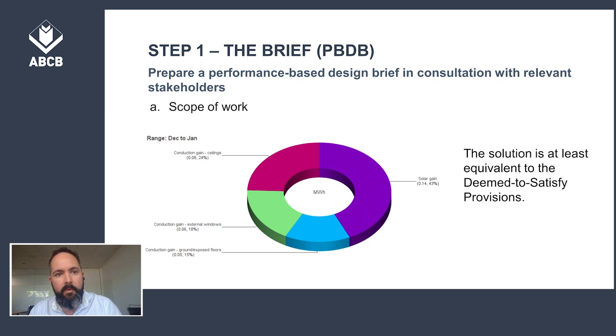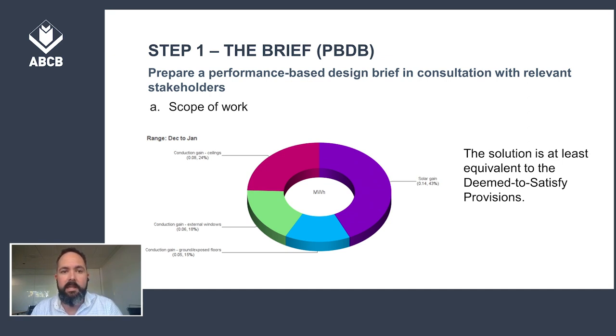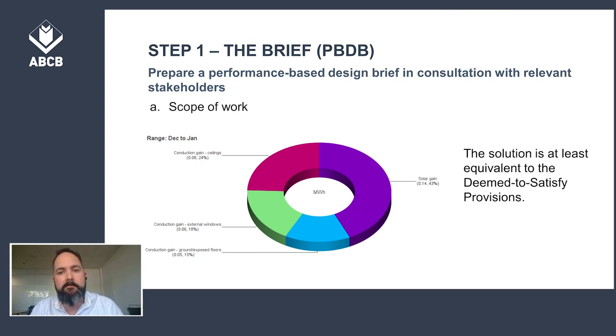Step one: prepare a performance based design brief, which includes a scope of works. The scope of works proposed by the stakeholder group is to undertake analysis to test whether the heating and cooling loads for the proposed building with no floor insulation are less than that of a reference building with deemed-to-satisfy compliant walls. It is proposed that the performance solution is achieved by demonstrating the solution is at least equivalent to the deemed-to-satisfy provisions, and as such comparison with the deemed-to-satisfy provisions is used as the assessment method.